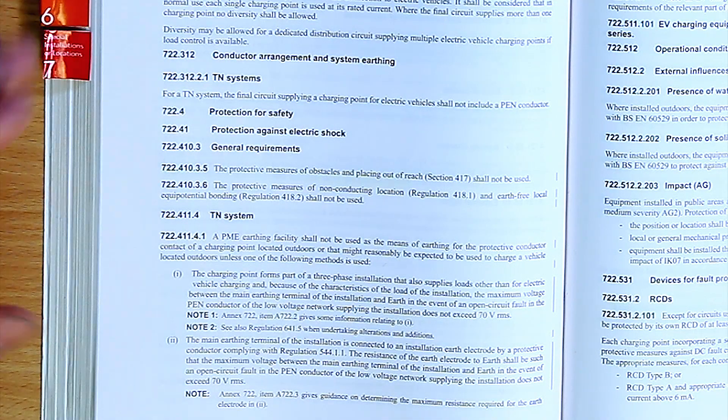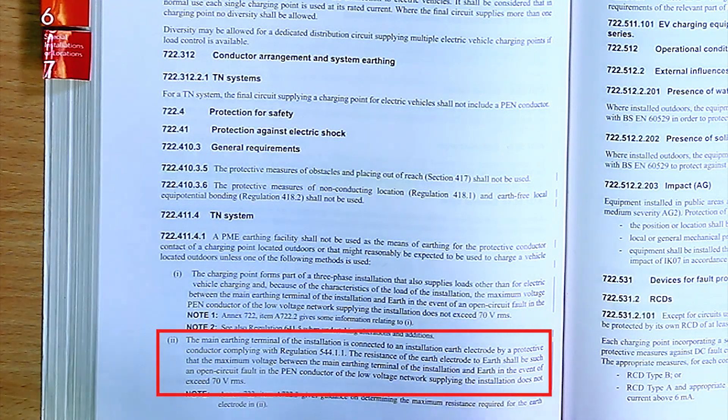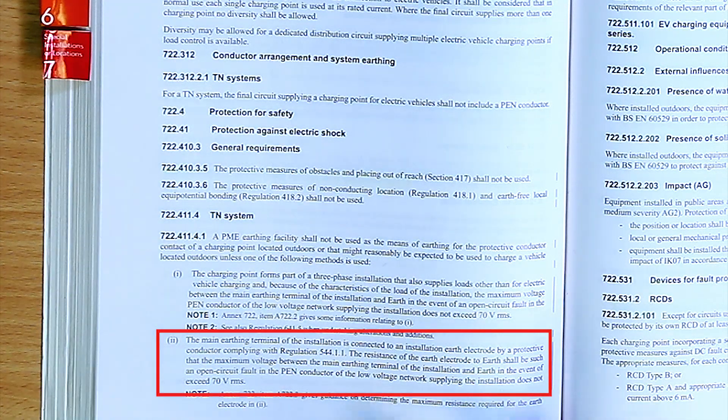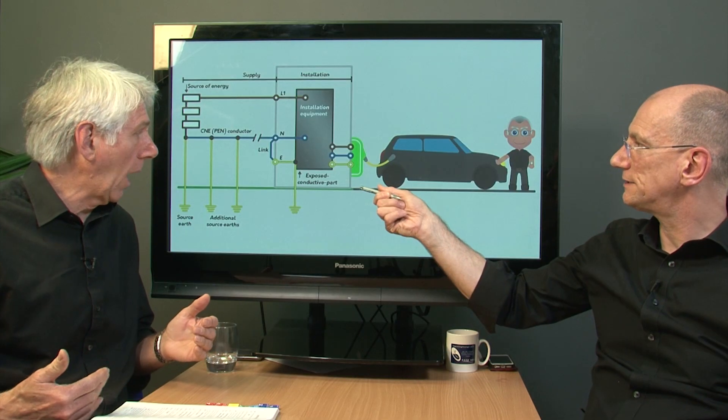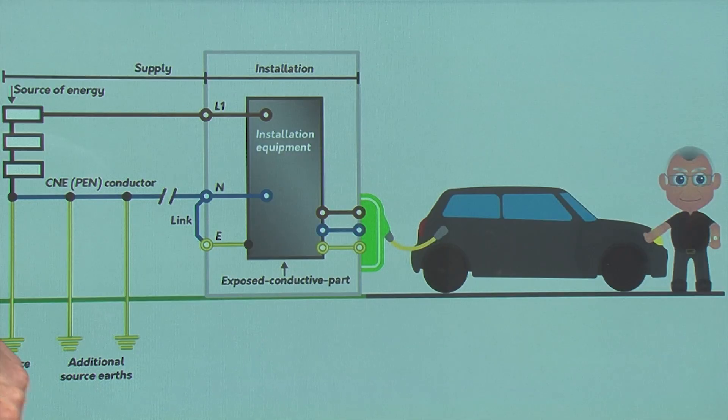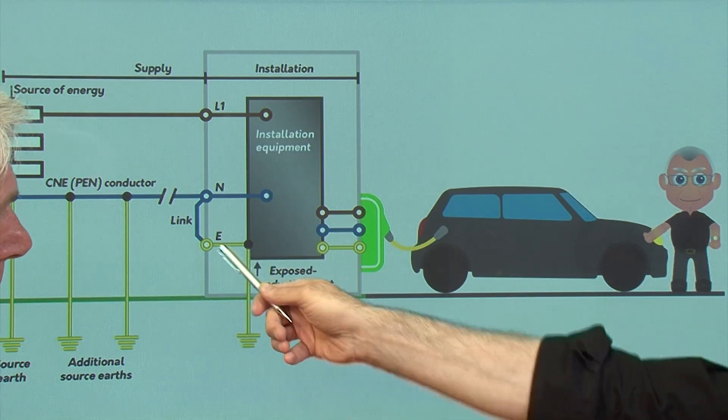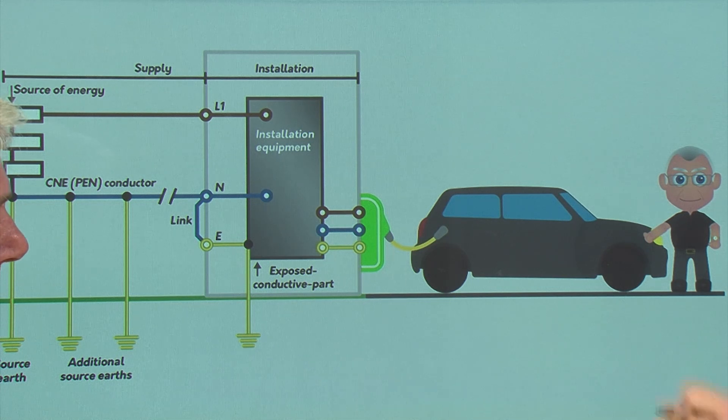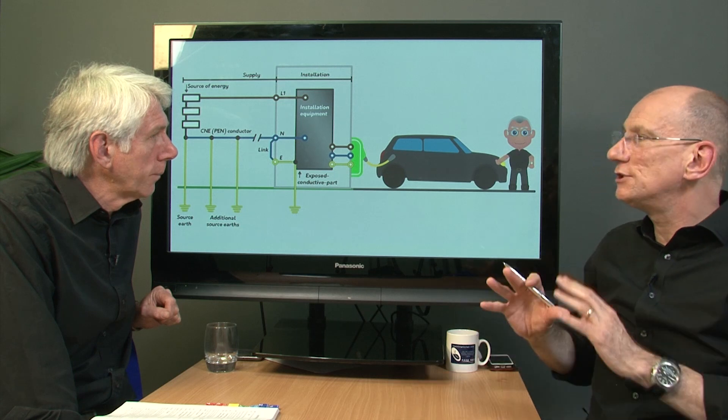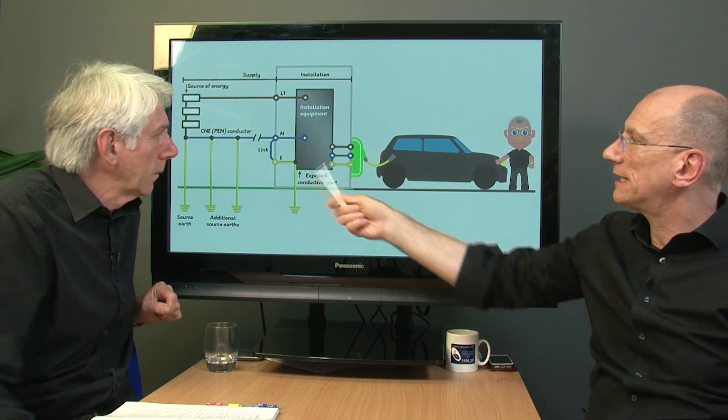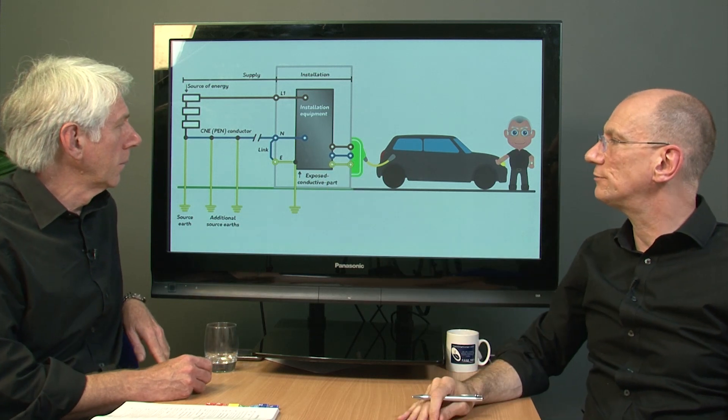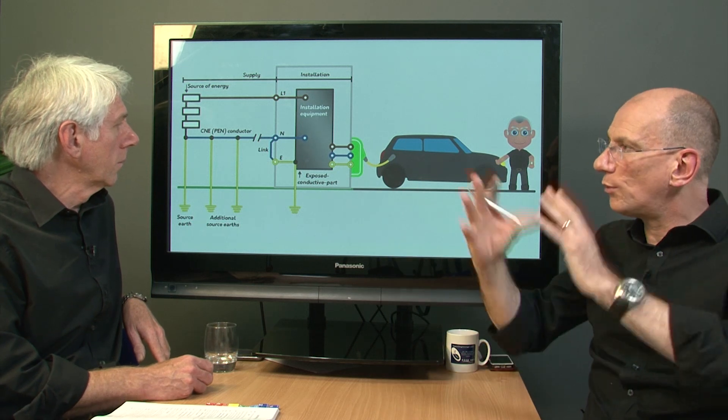Number two then. The main earthing terminal of the installation is connected to an installation earth electrode by a protective conductor. And it goes on to detail. Just like this. But like that. So let me just flip between the two. So basically, I mean, it's shown there. It's just for convenience there. But it's the main earthing terminal. This is the supplementary earth electrode. This is not TT. This is basically stating that if you end up with a broken neutral, there is an alternative path.